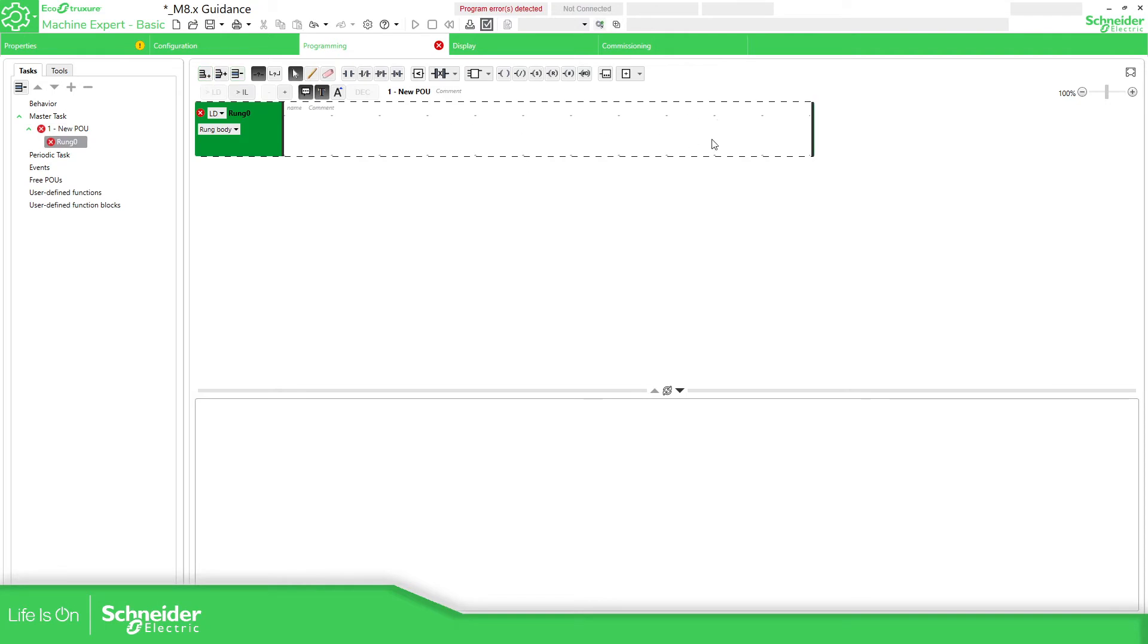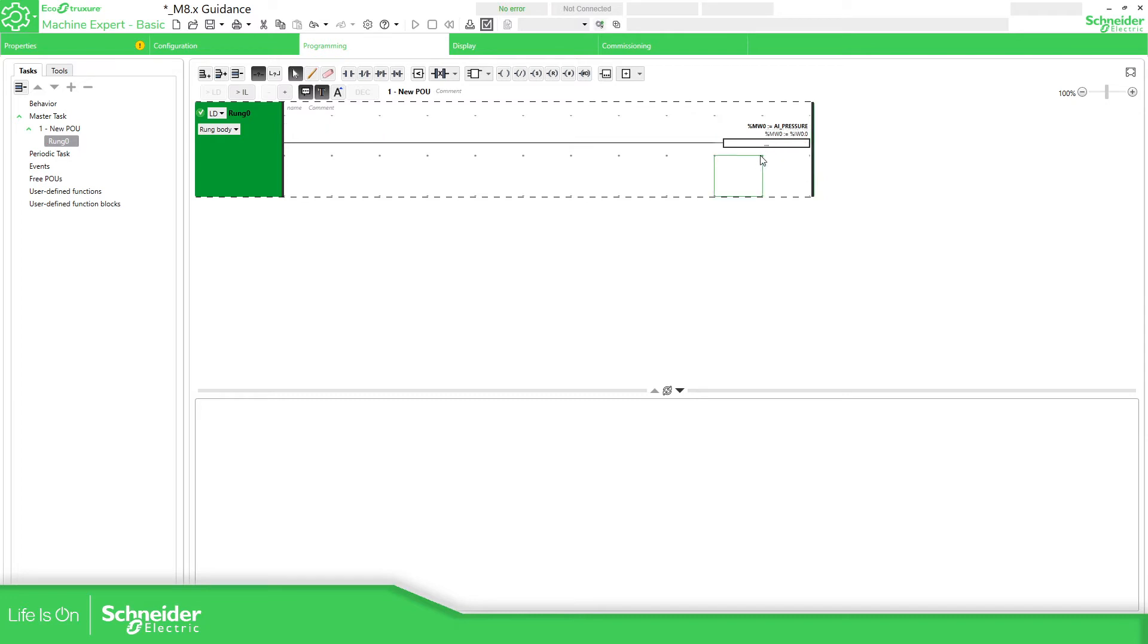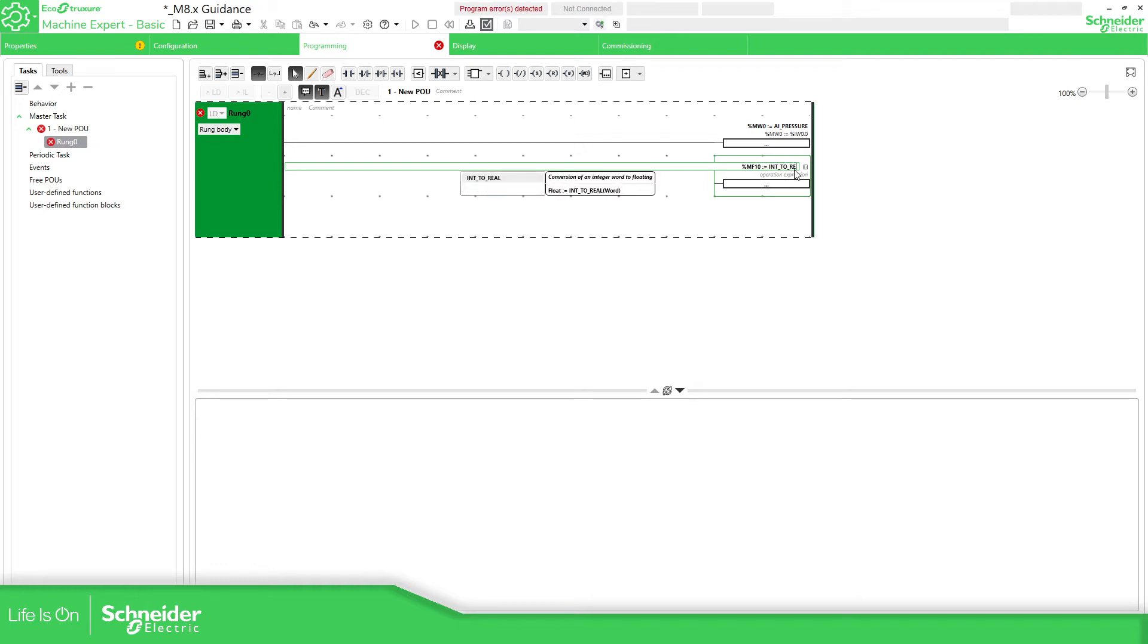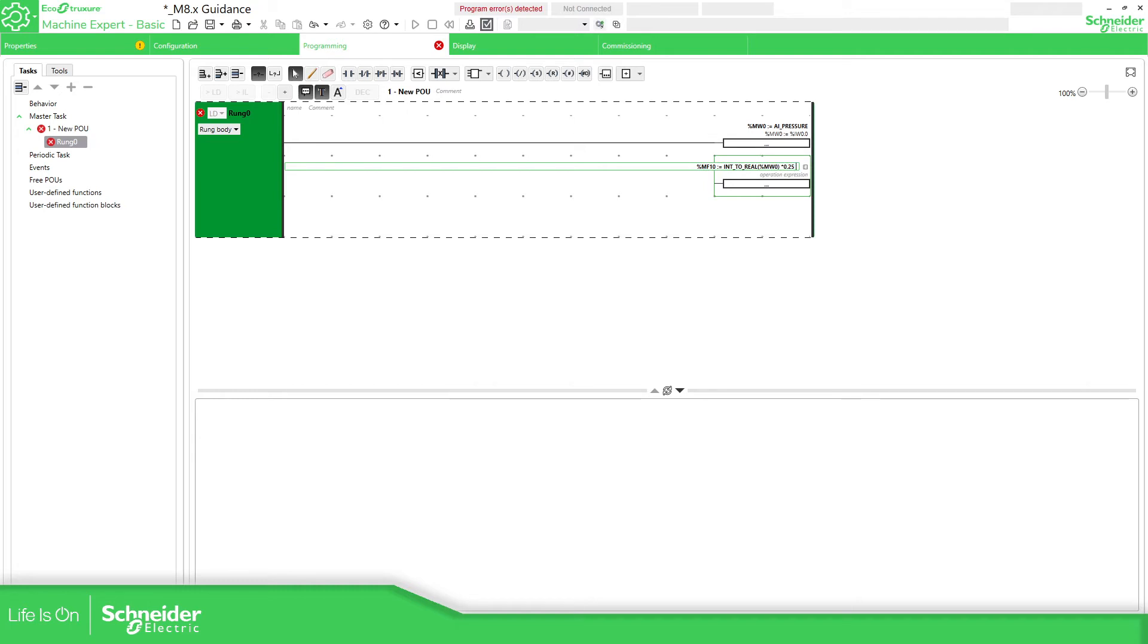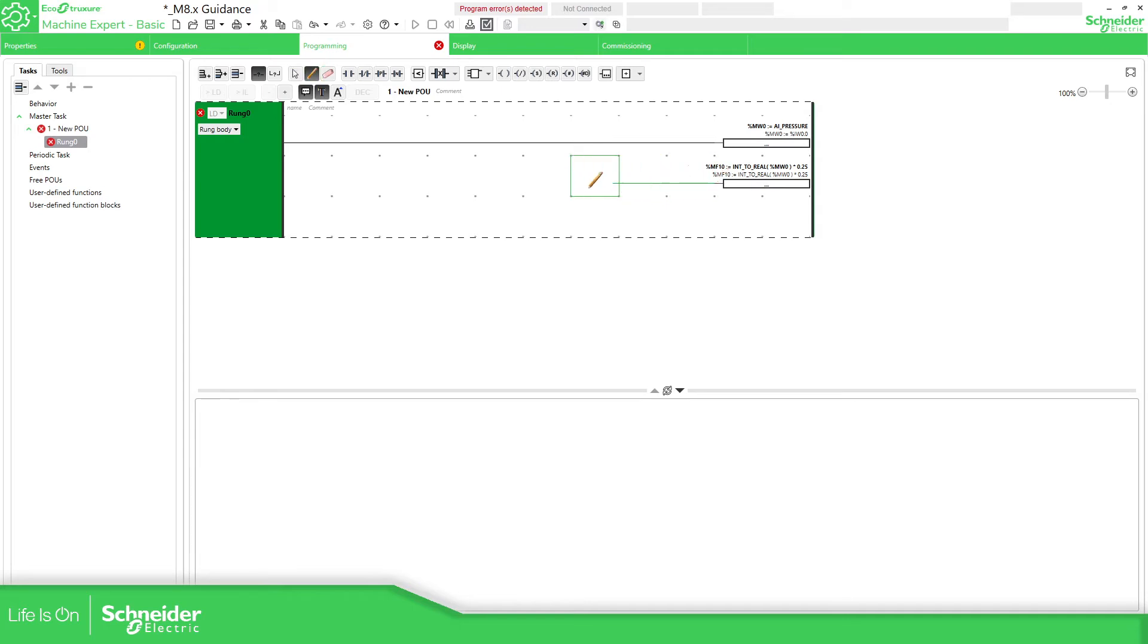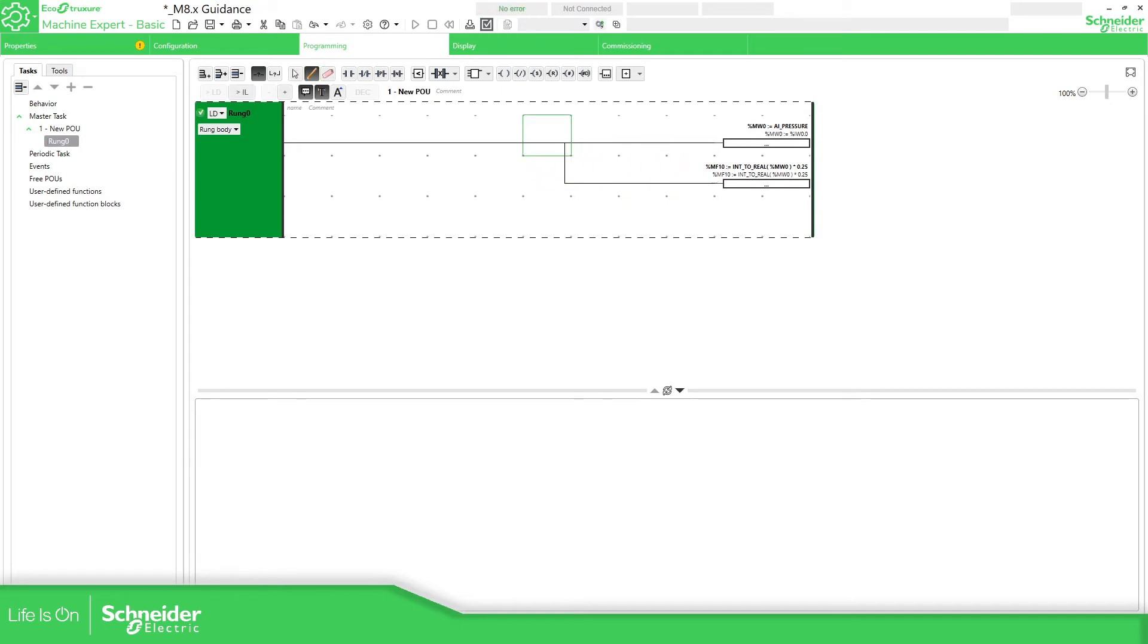In the programming, we can add a rung. In here, what we can do is assign an auxiliary variable, for example, %MW0 equal to the variable AI underscore pressure. Now what we need to do is transform this raw value into something that we can read. So it should be %MF10. Int_to_real - here, I need to use the auxiliary variable %MW, which is the raw value, multiply by the slope. Plus the offset part is 0, so I'm not going to put it.